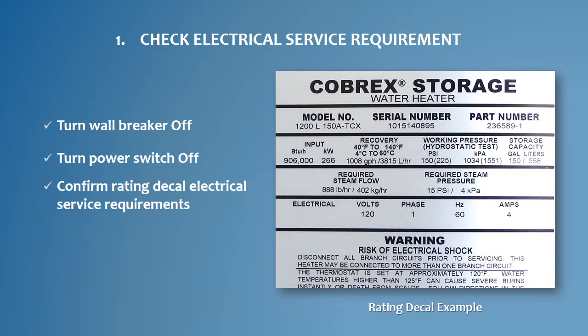Start by checking the electrical requirement for the water heater. Shut off the electrical service to the unit and turn the water heater power switch to the off position. The electrical service requirements are listed on the rating decal on the front of the storage tank. A standard product requires a 120 volt single phase 60 Hz power circuit that is also electrically grounded.